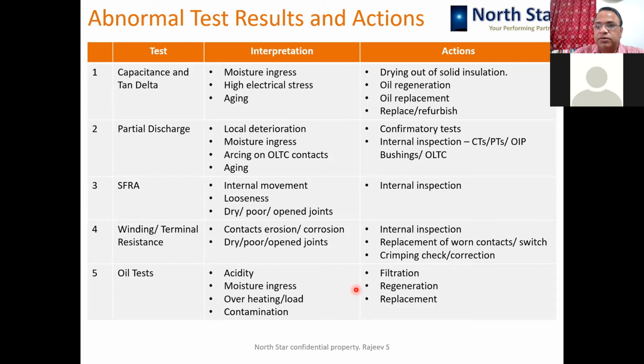Okay. Drying out of solid insulation, as we discussed, ultimately, when tan delta and capacitance tests are abnormal, decisions are to be taken based on the trends being noticed. So always today's test results are to be compared with the previous test results, and that way you should draw the trends and see the rate of deterioration. And if you find that there is a severe increase in the deterioration rate of the test values, then accordingly you can decide on the action of drying out the solid insulation. Because drying out of solid insulation is again a complex, time consuming activity. So it is to be done only when it is very much required.